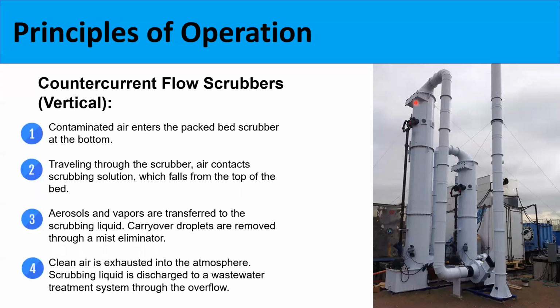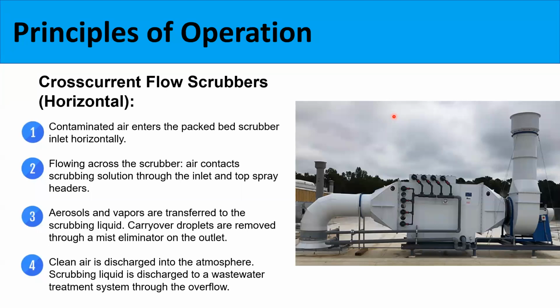Moving on, the next type of wet pack bed scrubber is the horizontal cross flow unit, again, as seen in the photo here. While this is very similar in principle of operation to the vertical countercurrent, the gas stream enters the scrubber on the left-hand side of this pictured unit and travels horizontally to the right side of the unit, while simultaneously the recirculated chemical stream or fresh water stream enters the scrubber towards the top of the unit and then travels down towards the sump of the unit, contacting the gas stream again in the pack bed section, absorbing the contaminant and allowing it to be collected or discharged from the sump. Again, hence we've got the term cross flow.